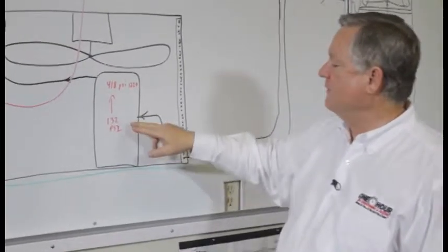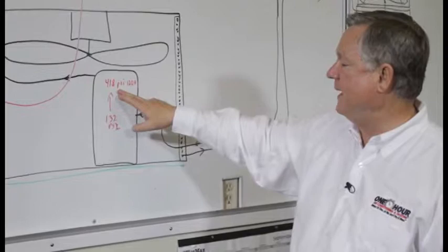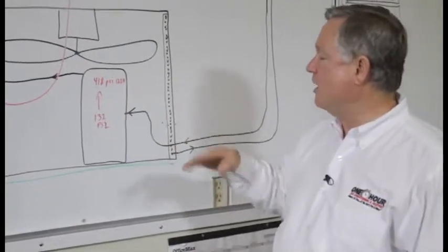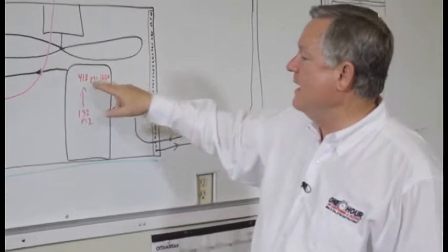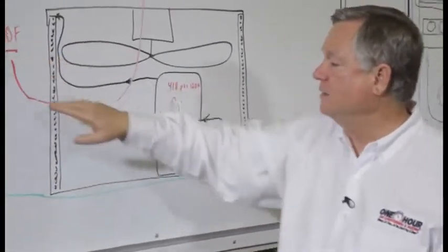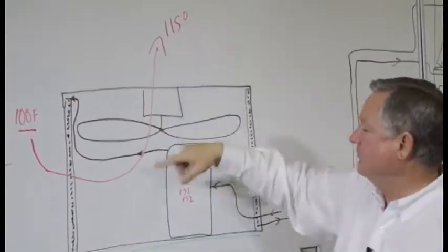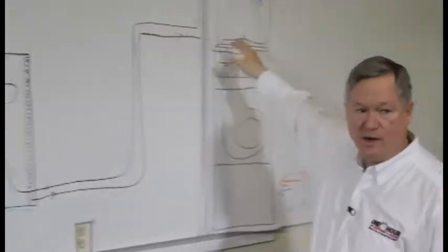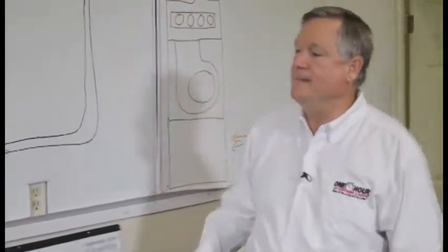You know, the small two lines, the refrigerant's coming back to a compressor. Typical installation, if it needs to go from 132 pounds to 418 pounds, that increase in pressure causes the refrigerant to get hot, heat up to 120 degrees, and then it goes through a fin tube coil where hot outside air is then warmed by the coil, removing that heat from the refrigerant. Then it goes back inside, chills the air, and you have refrigerated air. That's the way it works.